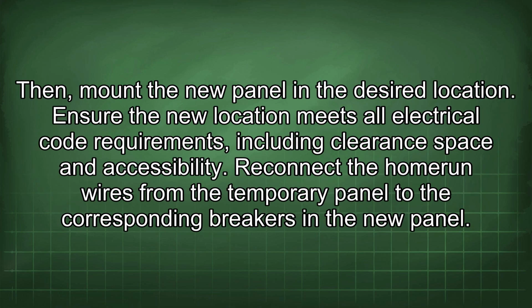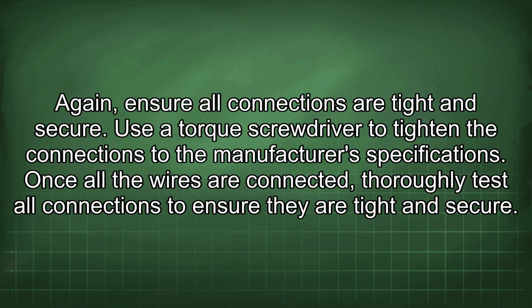Then mount the new panel in the desired location. Ensure the new location meets all electrical code requirements, including clearance space and accessibility. Reconnect the homerun wires from the temporary panel to the corresponding breakers in the new panel. Again, ensure all connections are tight and secure. Use a torque screwdriver to tighten the connections to the manufacturer's specifications.